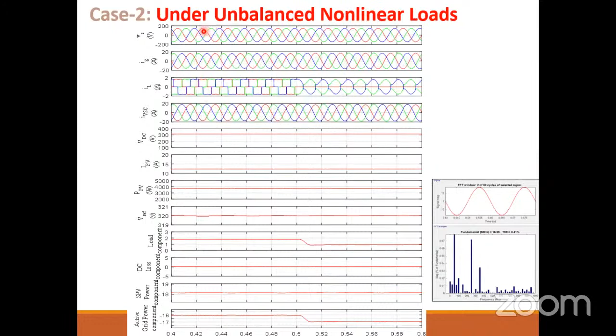This is the load current, the dark green color. This is your load current, a highly nonlinear current. But at the same time, the grid current is purely sinusoidal. Why is this? Because our inverter is generating the harmonics for this load. So if you look at the inverter current, it is not purely sinusoidal, because it is the addition of the grid current and this nonlinear load current. The inverter is generating harmonic current for the loads and the rest of the power as a pure sinusoidal for the grid. So this is the combination of both. That's why it looks this way.